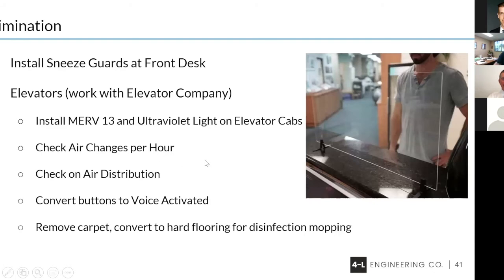Some of the things that we've done for improvements, which I see a lot of people already have, are sneeze guards. But now we're going to be talking a little bit about elevators. And Bob's going to dwell more on this in the future slides here. Just remember that one, concentrate on MERV 13 filters. You'll use UV lights to try to control it. You need to look at the amount of air changes that goes through the room. And all you have to do is calculate the volume of the room and use the CFMs to determine the air changes. Look at voice activated buttons to control.